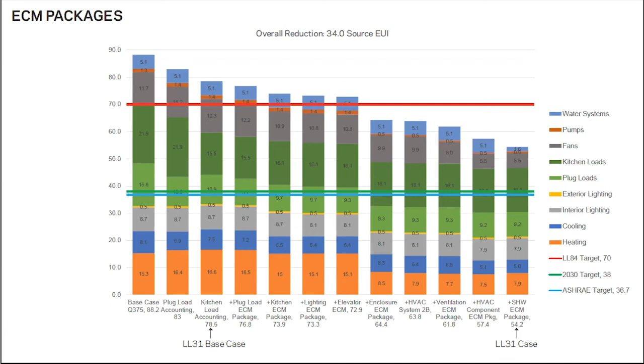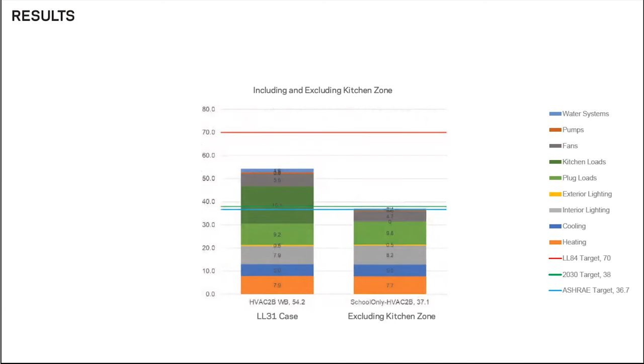So you would first think that, man, we didn't reach our goal. The whole point of the study was hopefully to get to 38 kBTU per square foot per year. But we did look at these numbers a little bit differently. If you just take out the commercial kitchen, the rest of the school does achieve the 38 kBTU per square foot goal, which we think is a win, a success story, as the 38 kBTU per square foot per year was not initially designed for commercial kitchen use.